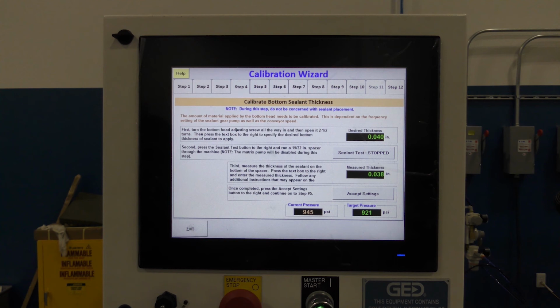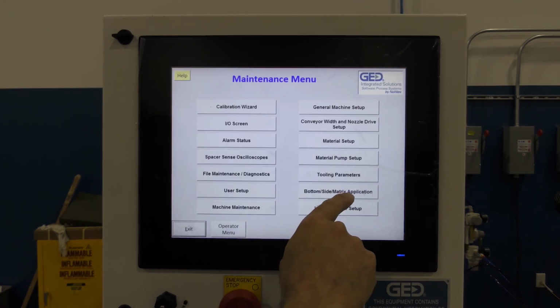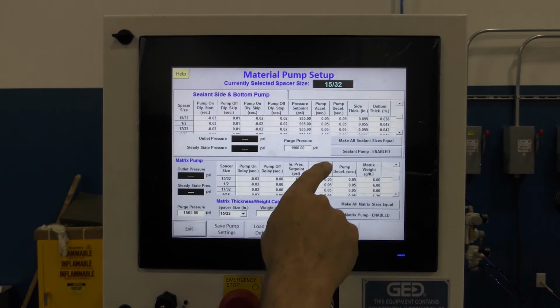If unsure, count the number of turns in and set it back to where it was. Run another spacer, and if the pressure and thickness are okay, then do nothing more. If the pressure and thickness are slightly off, then enter the measured thickness and continue the process until all is acceptable.